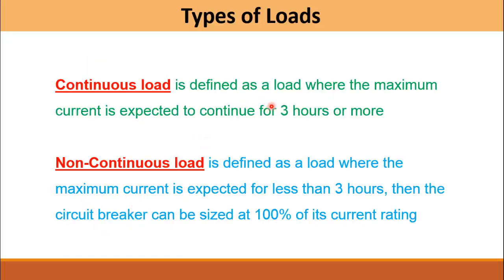The continuous load is defined as the load where the maximum current is expected to continue for three hours or more — for such loads, the circuit breaker is sized at 125% of the full load current. The non-continuous load is defined as the load where the maximum current is expected for less than three hours, so the circuit breaker can be sized at 100% of its maximum current rating.